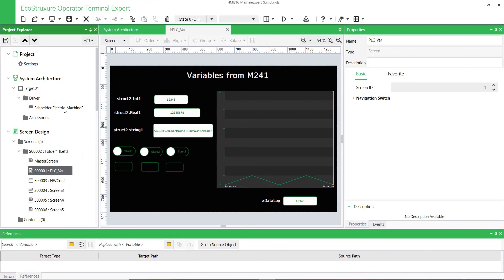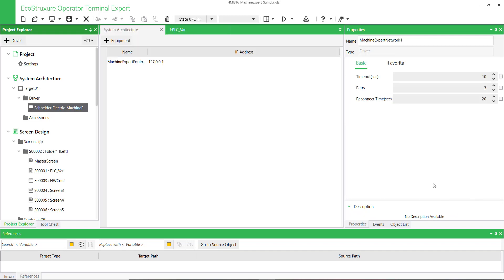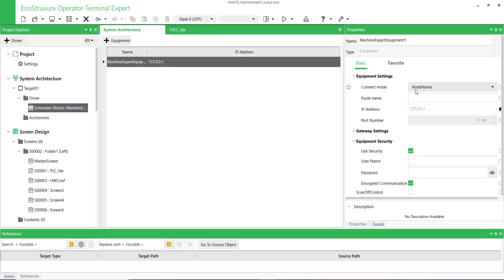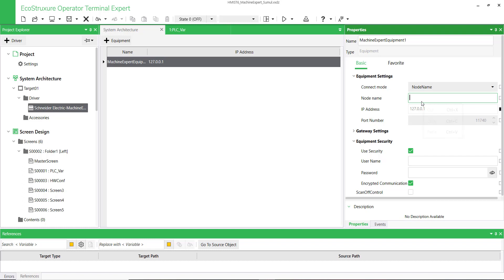Now switch to EcoStruxure Operator Terminal Expert to configure the driver. Click on Machine Expert Equipment and display the equipment settings. Keep the Node Name as connection mode — M241 and M251 support only the Node Name as connection mode. Paste the PLC node name.